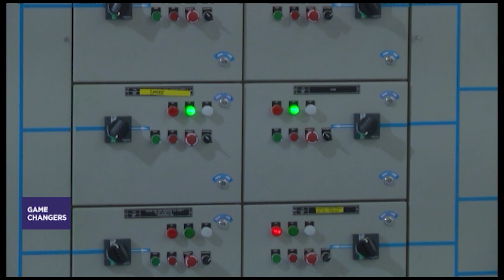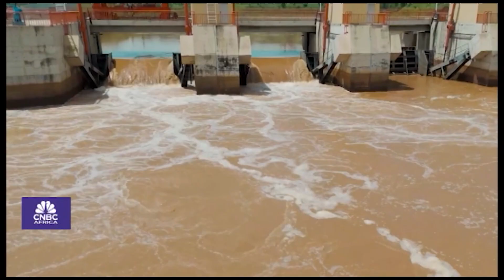To do that regulation, we use the governor. This structure you see in the brown, that's where inside we have a governor, but it also has its digital control on those control panels. With the governor, the operator can see the frequency, or in easy language, how much you are producing and how much the clients are requiring, so that we have a balance. The generation depends on the demand from the utilities and the water availability of that day.